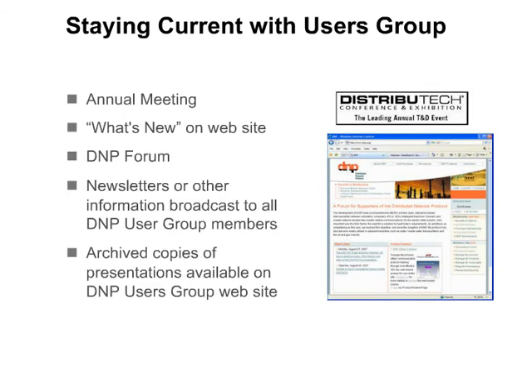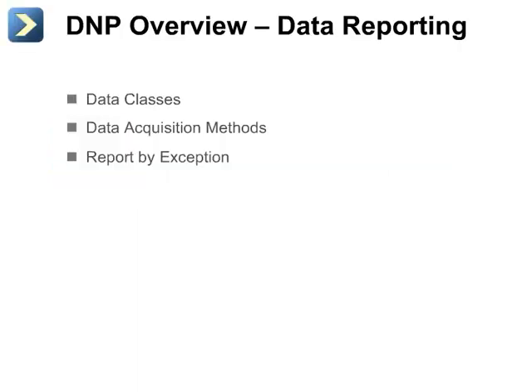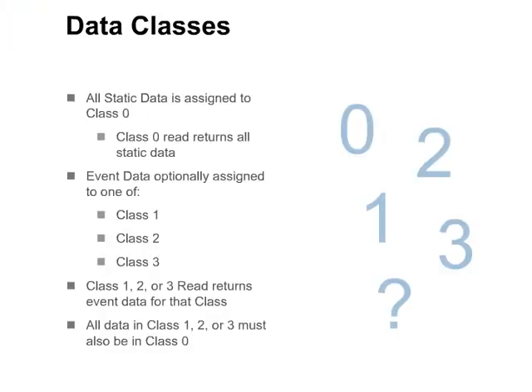Now let's take a closer look at the protocol itself. We'll discuss data acquisition methods, data classes, and report by exception. In DNP-3, static data refers to a point's current value. It is common for a class 0 poll to return all points in the outstation, though this is not required. Points not returned by a class 0 poll can only be read by direct reads. DNP requires that any points in class 1, 2, or 3 must also be in class 0. Data can be in class 0 and not be in class 1, 2, or 3, however.